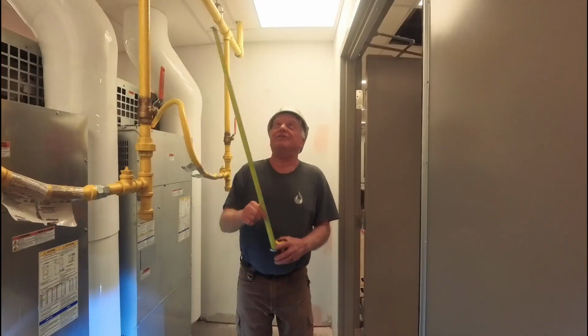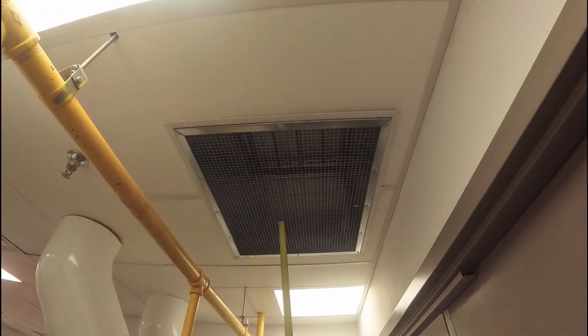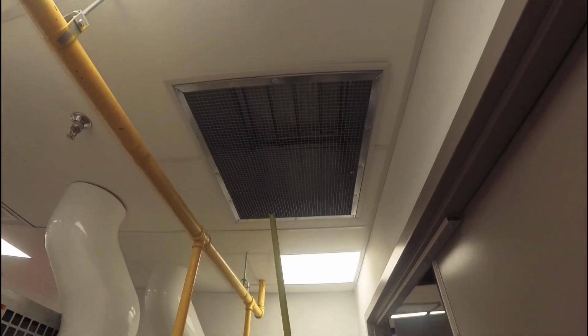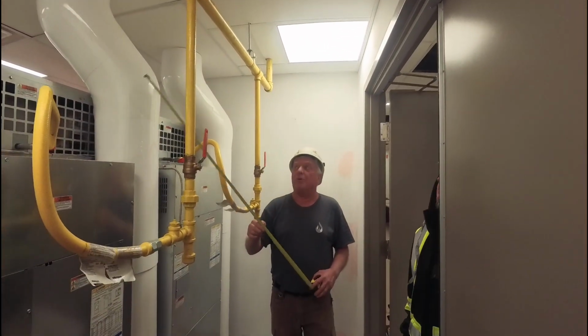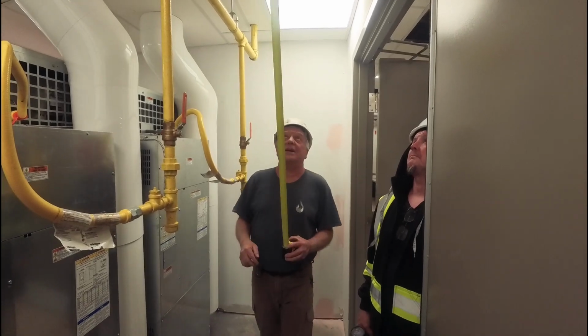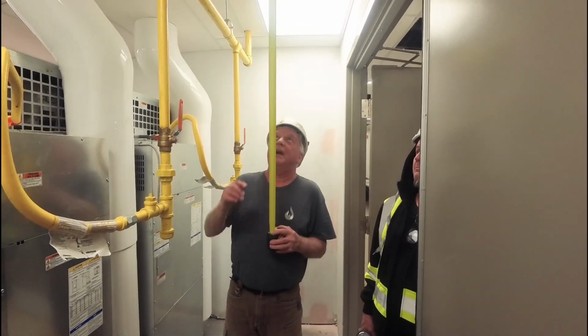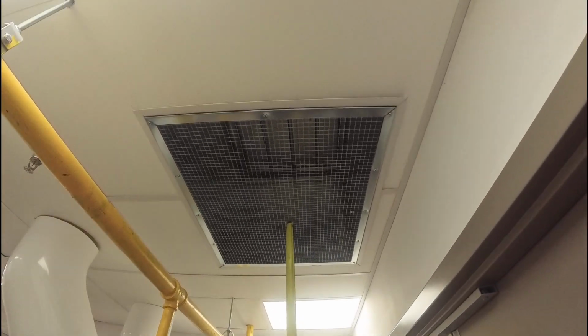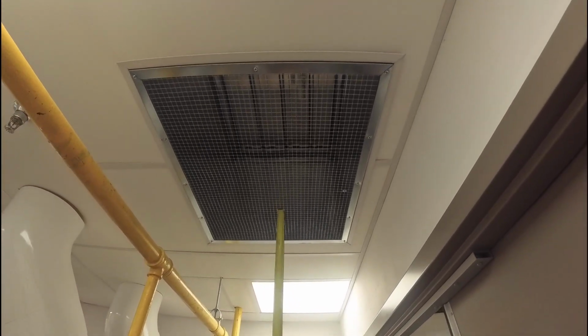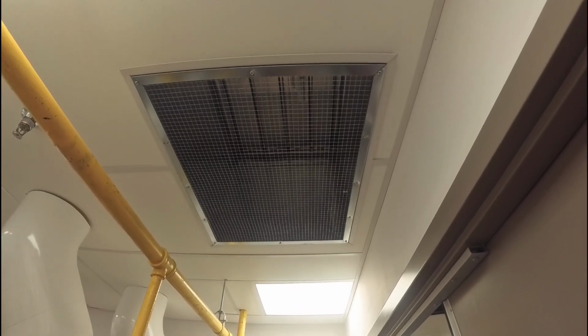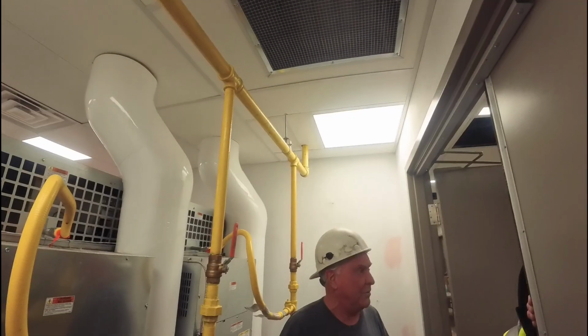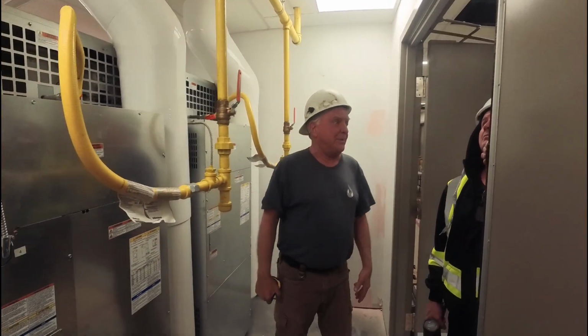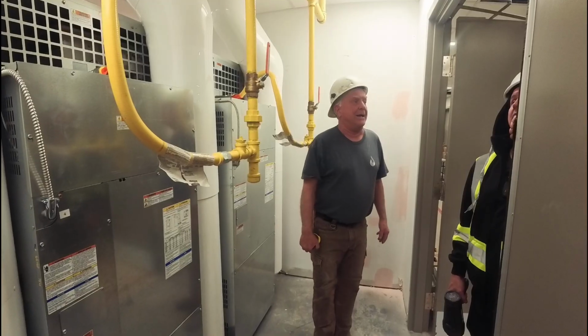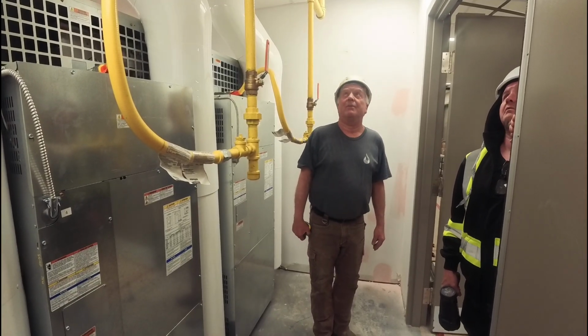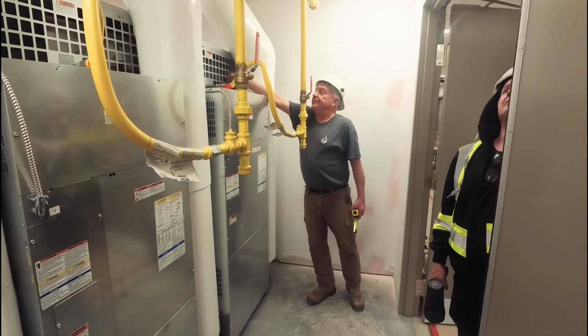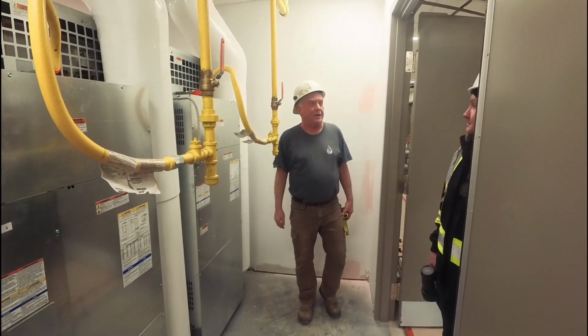So this is the makeup air, because the laundry facility is pulling so much air out of the dryers. It needs so much air to dry the clothes. This has a motorized damper, you can see, which is in the closed position, and the motor is associated with when the dryers get turned on. That damper will open up, which will now pull cold air from outside and replace the air, makeup air. Whenever you remove air from the room, you've got to bring adequate air back in, right? I see. Okay. That's what that one's for. There's your air for the dryers in the back area here.